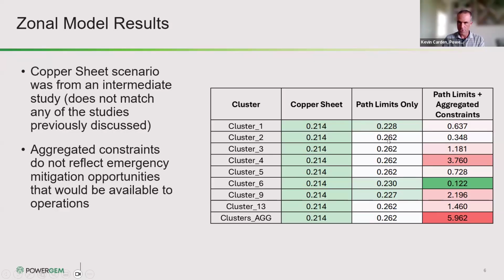This is essentially 1 event in 100 years of additional reliability events due to that transfer constraint. Clusters 2 through 5, and cluster 13, all have their events concentrated at the same time. 2, 3, 4, 5 can transfer enough power, but they can't get power from 6, 9, and 1 as needed to satisfy reliability events. There are some constraints between zones 1, 6, and 9 to get to the other zones. So overall, we're adding 1 or 2 events in 100 years due to these path limits only.